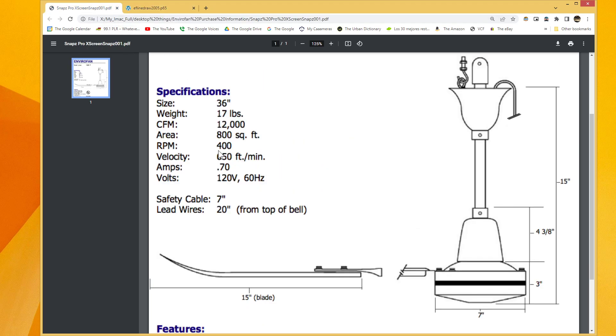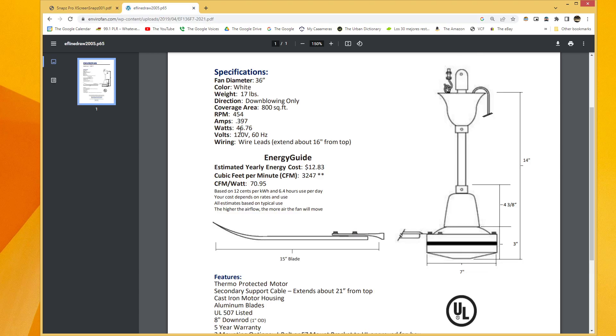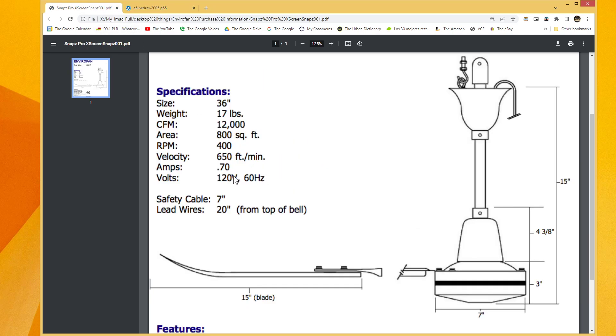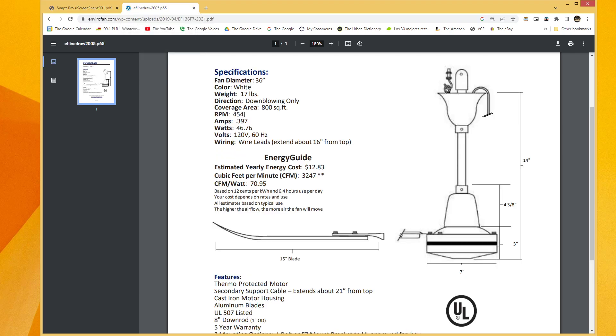Curiously, the old one spins at 400 RPM, draws 0.7 amps. The new one spins at 454 RPMs, which is outrageously fast, and it only draws 0.4 as opposed to 0.7. We don't have watts on the other one, but I would assume it's power factor at least 0.95 or higher, because it's a PSC motor. So, very, very interesting.